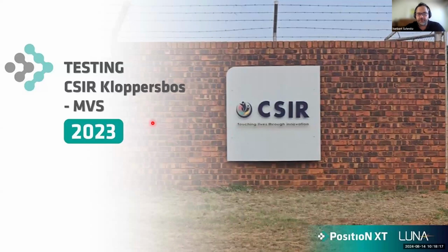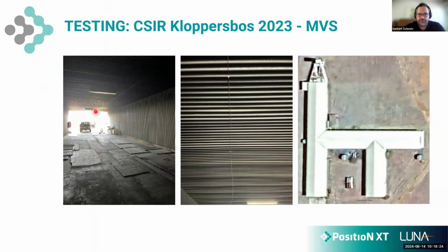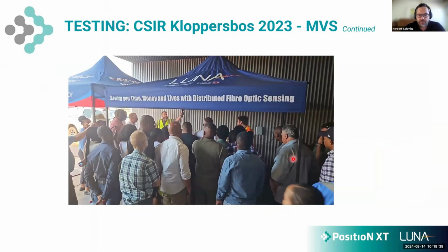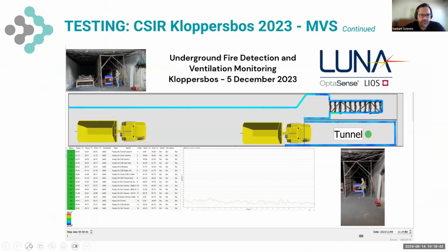So through the years, we've done quite a bit of testing. Most recently, end of last year, we installed the fiber optic sensor cable within a test mine ventilation tunnel. You can see the sensor cable running on the ceiling there, on the hanging wall within that section. And within this test, we simulated a fire within a mining machine, an LHD.